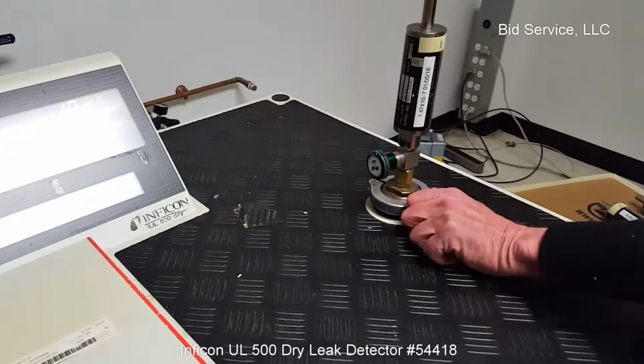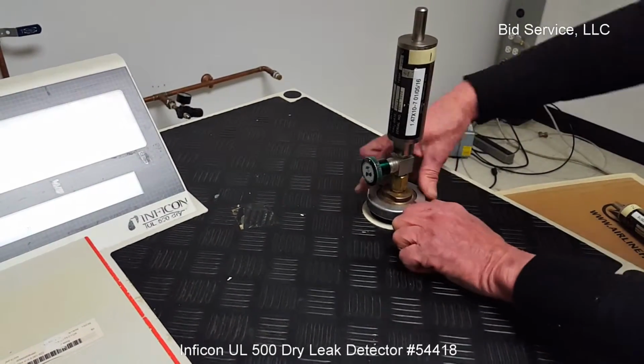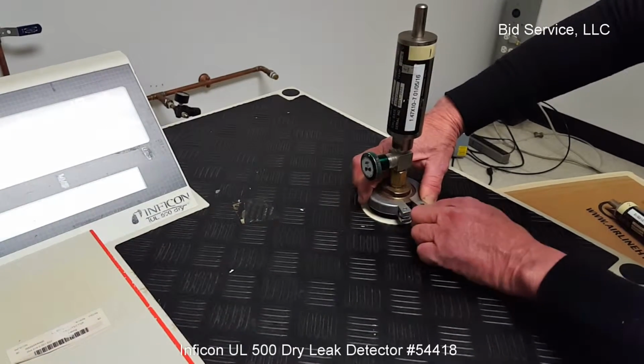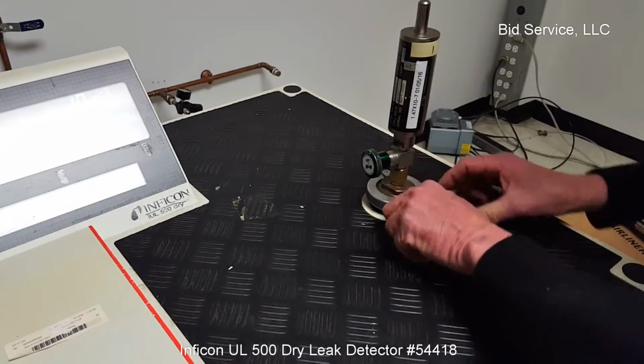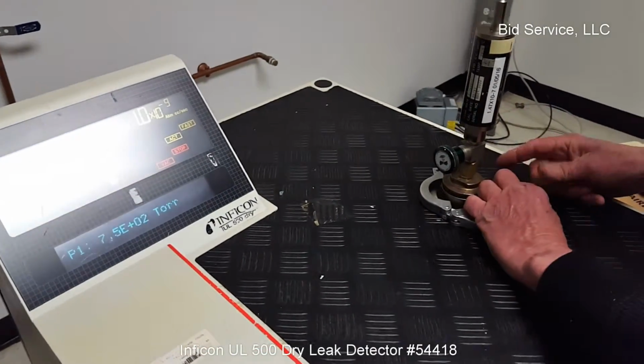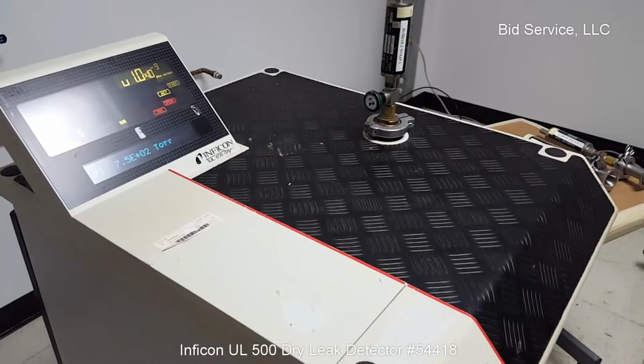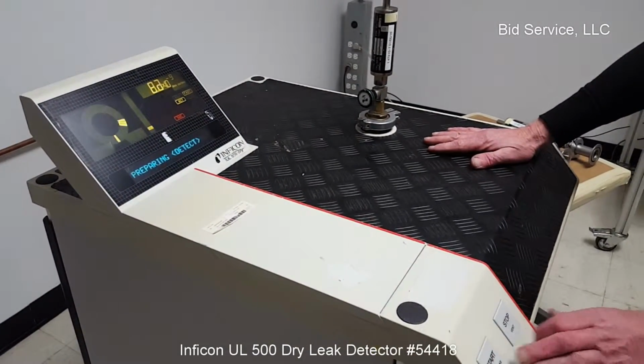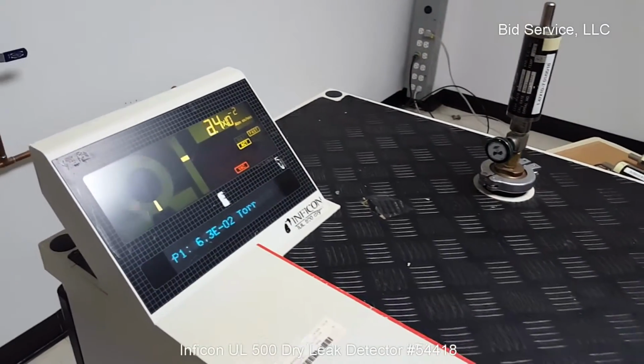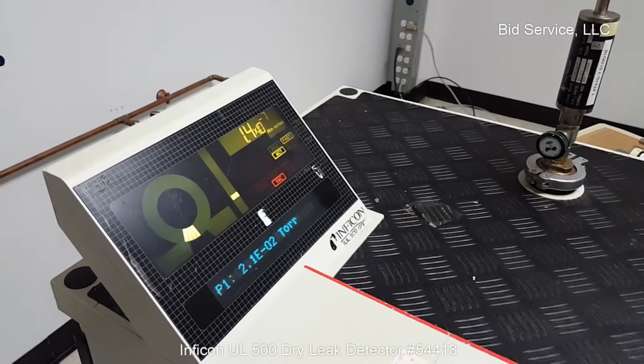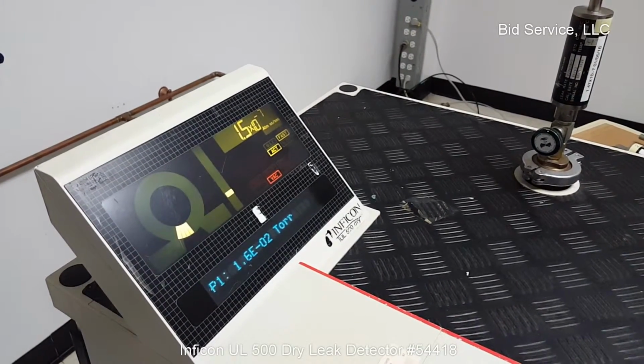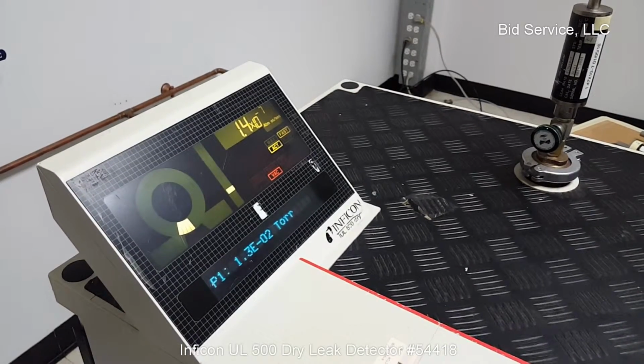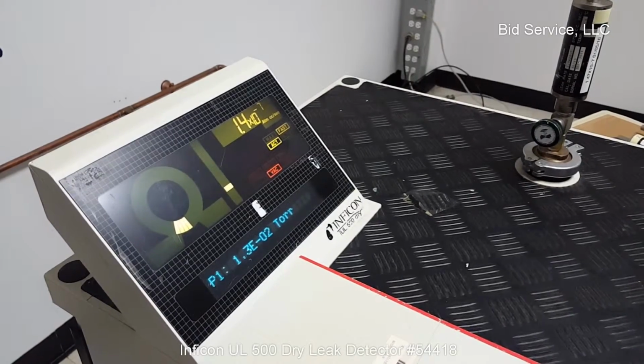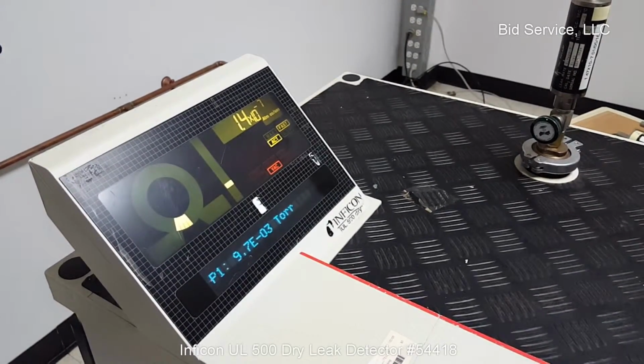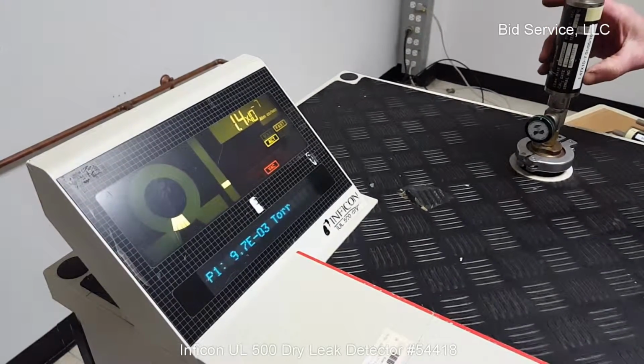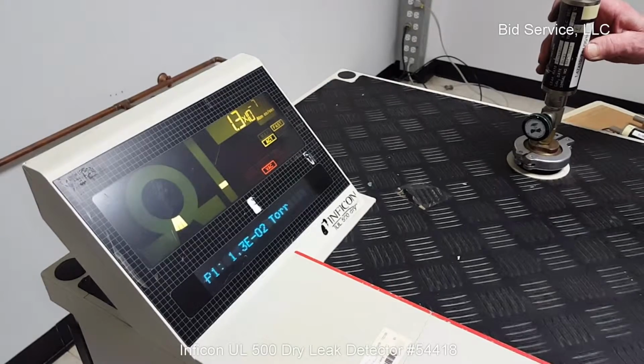These calibrated leak sources have also been checked on other systems and compared to make sure that they're within an accurate range. Okay, we will just simply push start. And the Leybold system reads 1.4 times 10 to the minus 7. And our leak source is 1.47 times 10 to the minus 7. Very, very close.